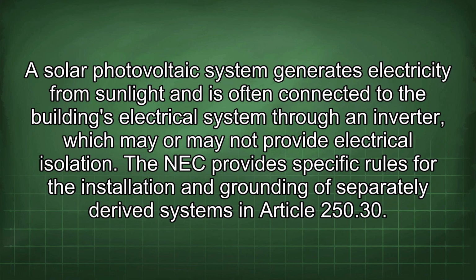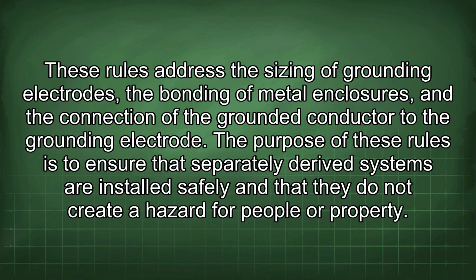The NEC provides specific rules for the installation and grounding of separately derived systems in Article 250.30. These rules address the sizing of grounding electrodes, the bonding of metal enclosures, and the connection of the grounded conductor to the grounding electrode. The purpose of these rules is to ensure that separately derived systems are installed safely and that they do not create a hazard for people or property.